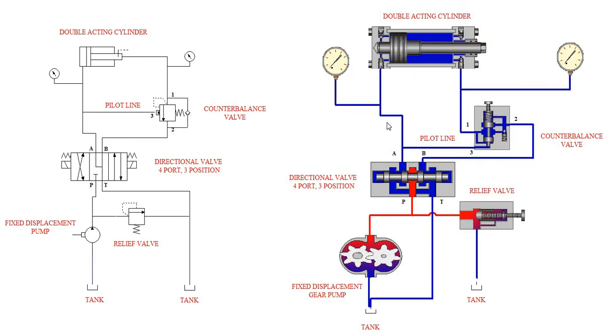So now we'll take it frame by frame, and as you can see here, when we start off, the spool is in the neutral position. Flow from the pump is blocked. These lands right here can't go anywhere, so its only path is over the relief valve. And you can see the relief valve poppet is unseated, allowing this flow to flow through the valve into the tank. So the pressure here has exceeded the rating of the spring, allowing it to go to tank.